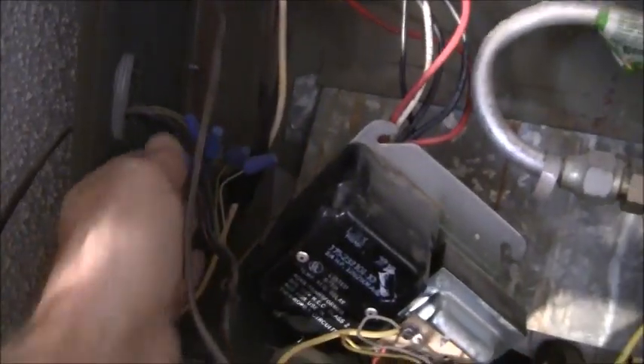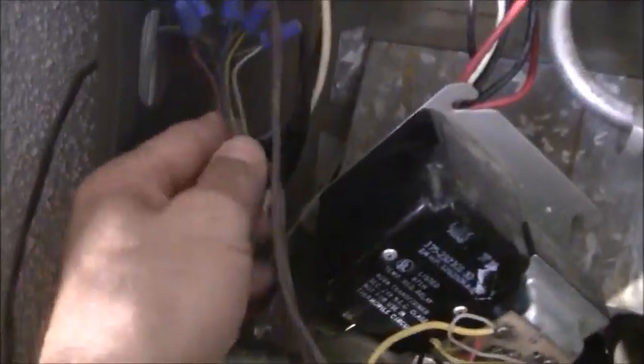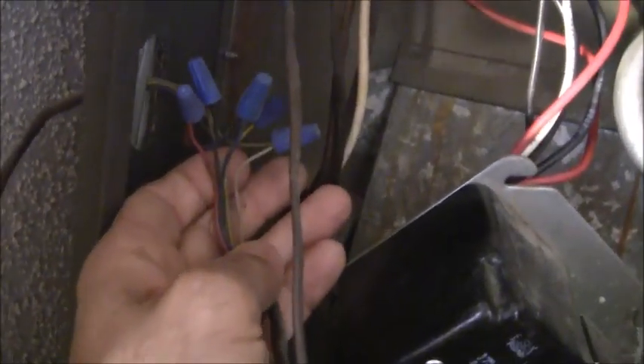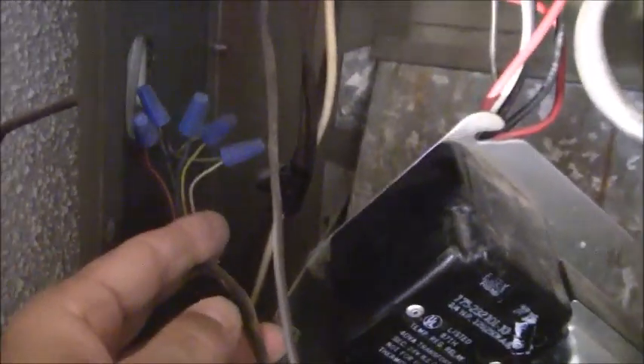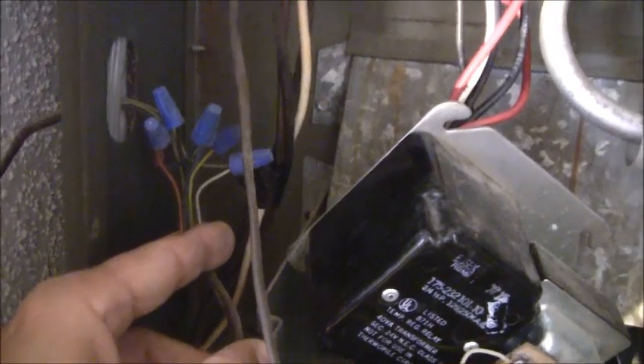Now when you're looking at the thermostat wires, you can see 2 sets — one set here and one set here. This one here, which goes up, has to go outside to the contactor, to the condenser outside. So if I follow my wiring, there are two wires here that are going to hit that contactor. This section here is going downstairs to the thermostat downstairs, so this is your heating, cooling, and fan operation thermostat.